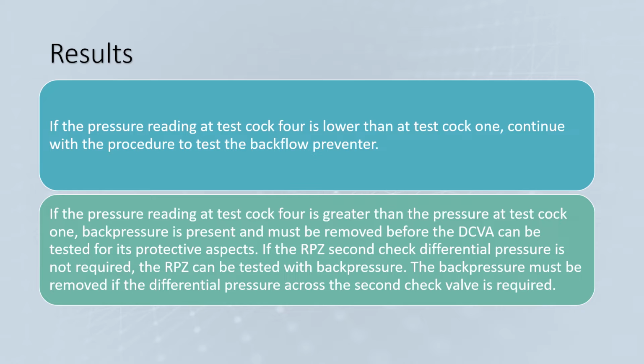Results. If the pressure reading at test cock 4 is lower than at test cock 1, continue with the procedure to test the backflow preventer. If the pressure reading at test cock 4 is greater than the pressure at test cock 1, back pressure is present and must be removed, before the DCVA can be tested for its protective aspects. If the RPZ second check differential pressure is not required, the RPZ can be tested with back pressure. The back pressure must be removed, if the differential pressure across the second check valve is required.